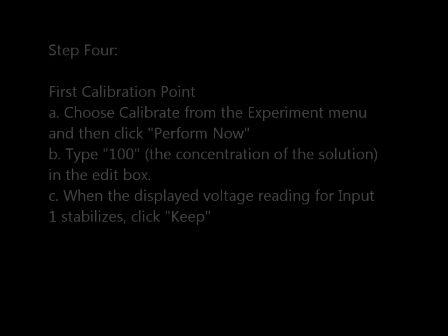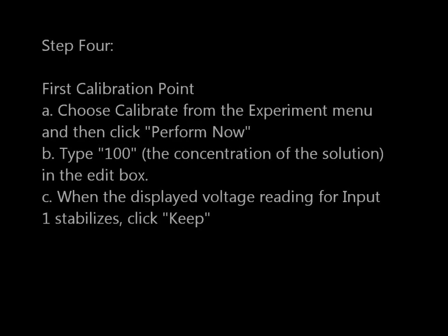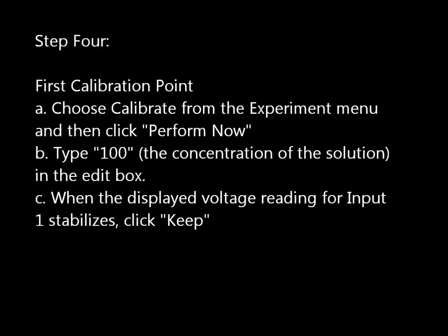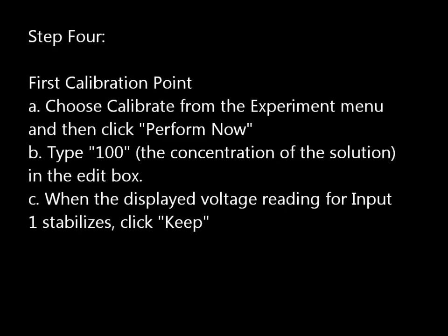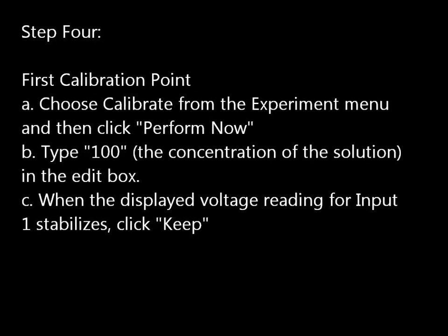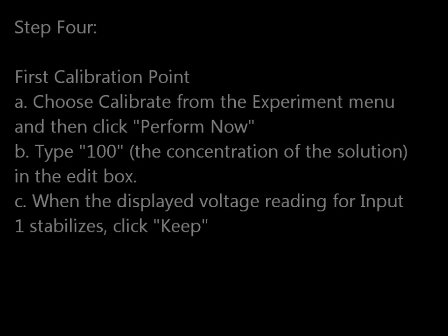Step 4. First calibration point. Choose Calibrate from the experiment menu and then click Perform Now. Type 100, the concentration of the solution, in the edit box. When the displayed voltage reading for input 1 stabilizes, click Keep.